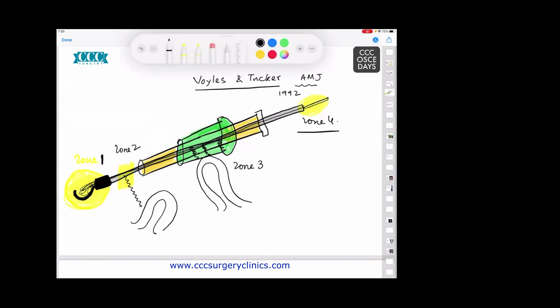While doing a lap chole, do you notice which part of the bowel or stomach, or what your port is touching? Majority of us do not get to notice, because the camera operator is showing you only the tip of the instrument. So the only moral from the whole story today is, please check the insulation of that device before you start operating. Please remember, check the insulation.